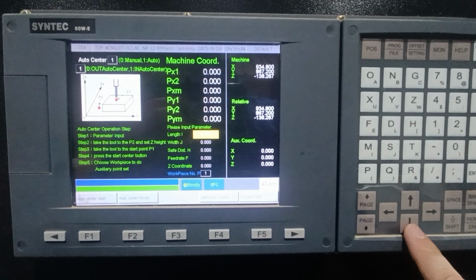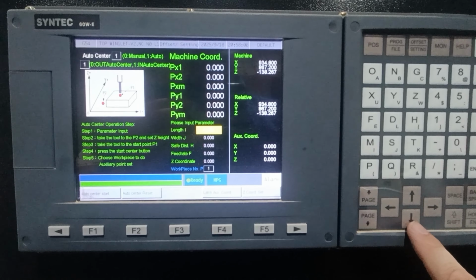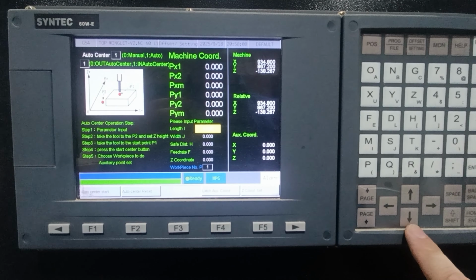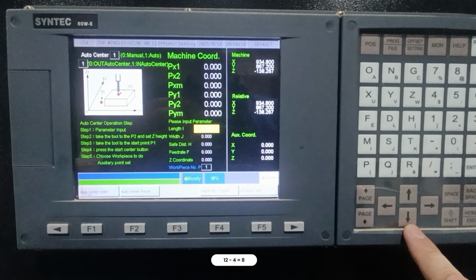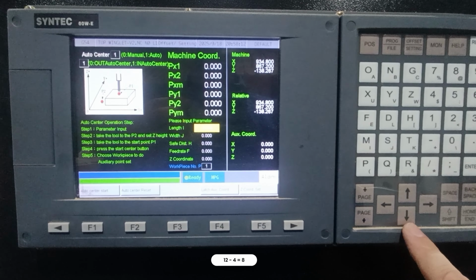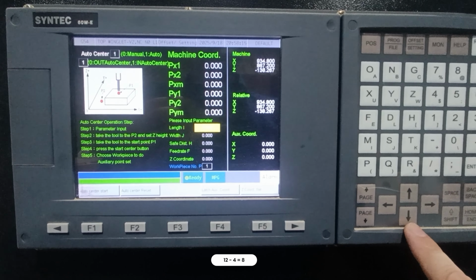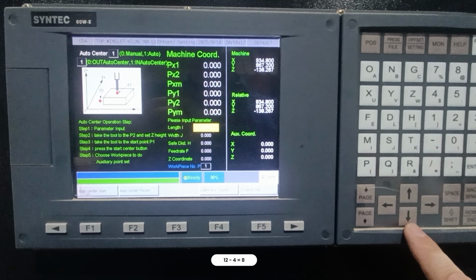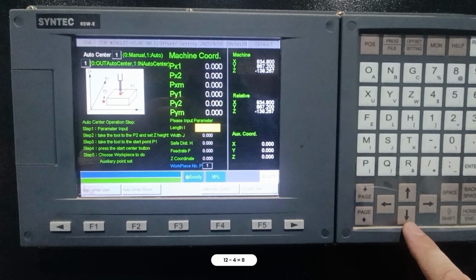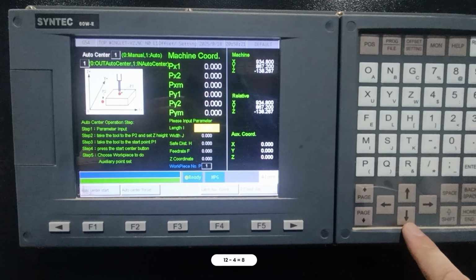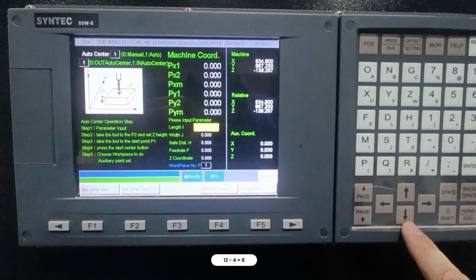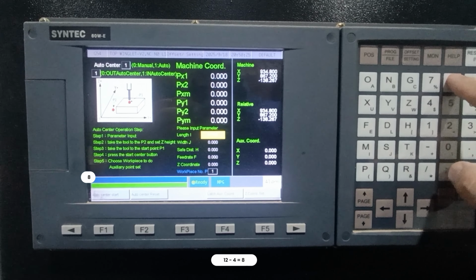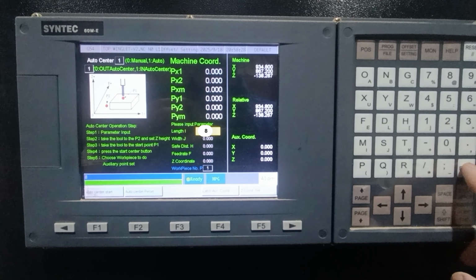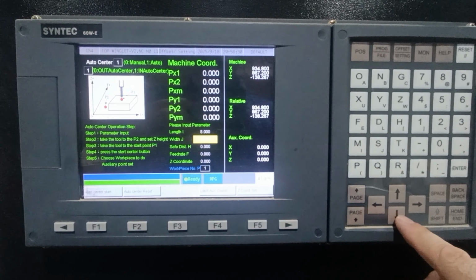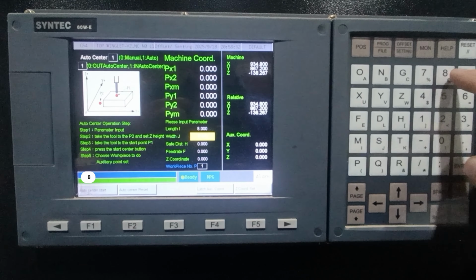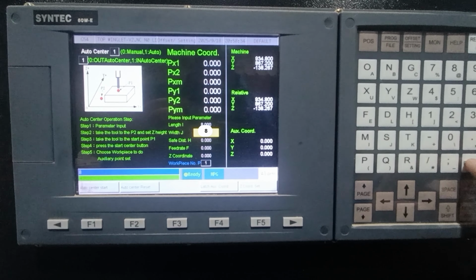Now we need to input the settings. I know that my hole I want to measure is 12 millimeter and the touch probe ball is 4 millimeter. Subtract it from each other and put in here the difference. So this is 8. Enter. Because it's a round hole, it's 2 times for X and Y, both 8.